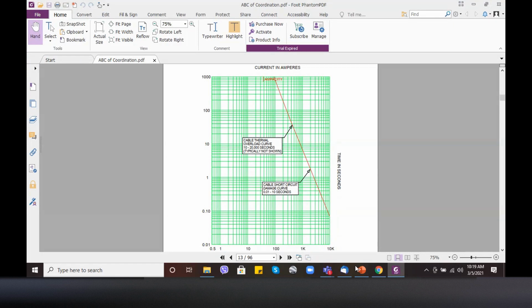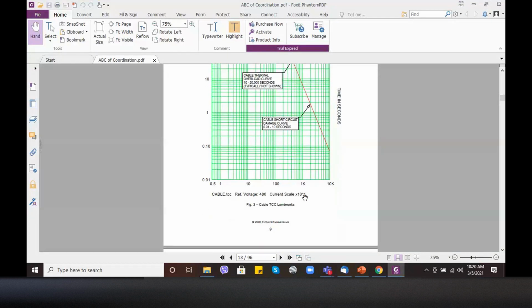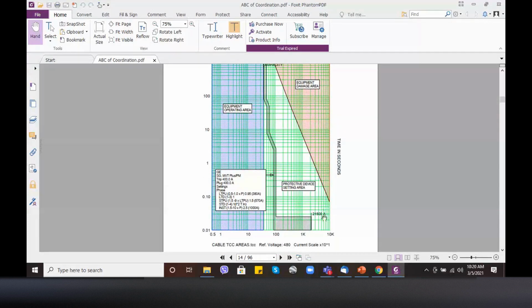So sa cable pala, we have two lines or two curves. The number one is the thermal overload curve and the other one is the damage curve or the short circuit curve. So basically, dapat ma-plot mo yan which depends on the application or type of cables na ginagamit mo sa planta. Para pag alam mong i-plot yan, this is called the TCC, time current curve. So para pag alam mong i-plot yan, you have to properly provide protection to the cable. So meaning, yung cable na yan, well protected ng devices na to.